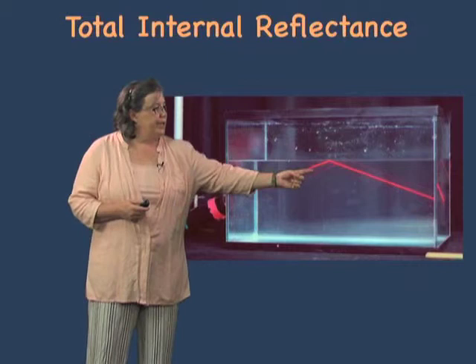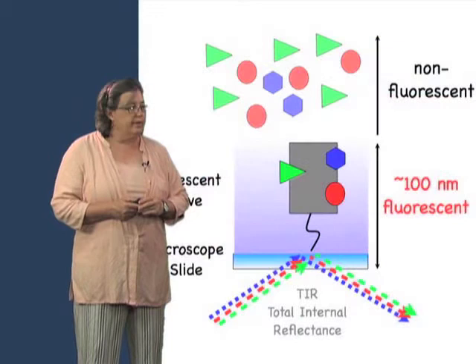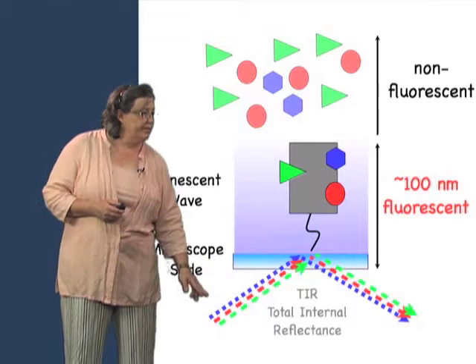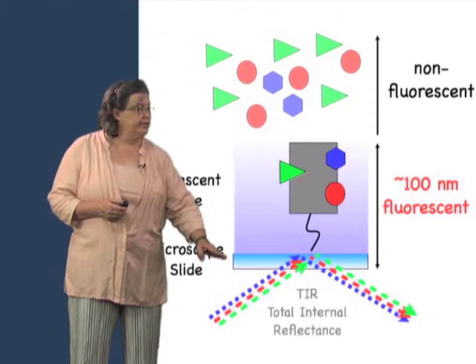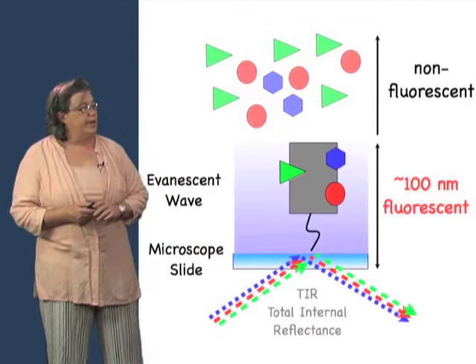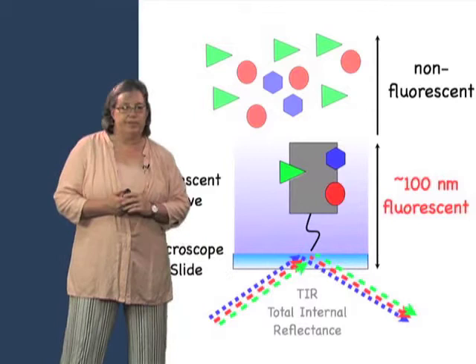Except right at the point where the laser contacts, there is a little bit of energy that goes to the other side called the evanescent wave. In this case, the lasers come through the air to a microscope slide, and here is the change in refractive indexes going from the microscope slide to the aqueous layer above it. The evanescent wave will go about 100 nanometers into the solution above the microscope slide. So imagine having not just one laser, but three different colors of lasers.